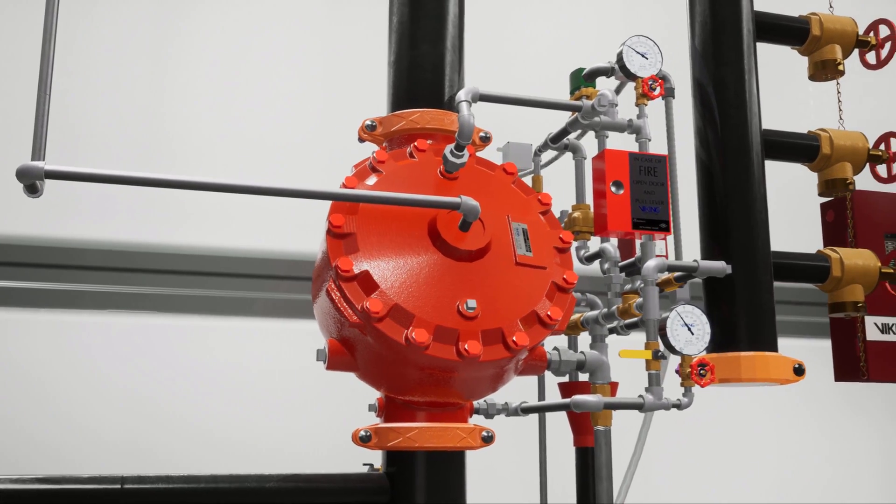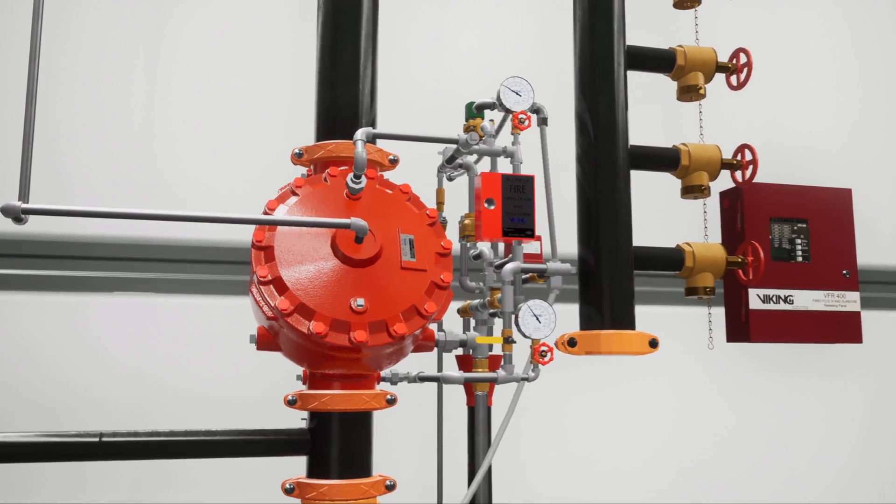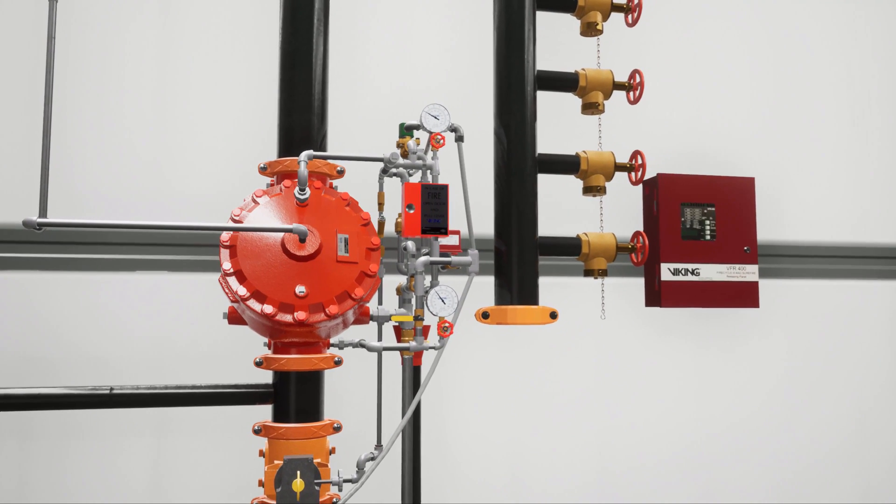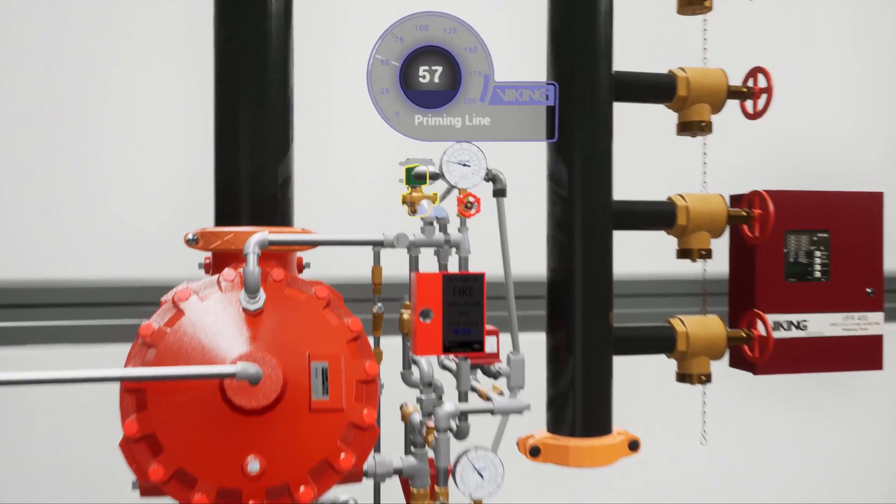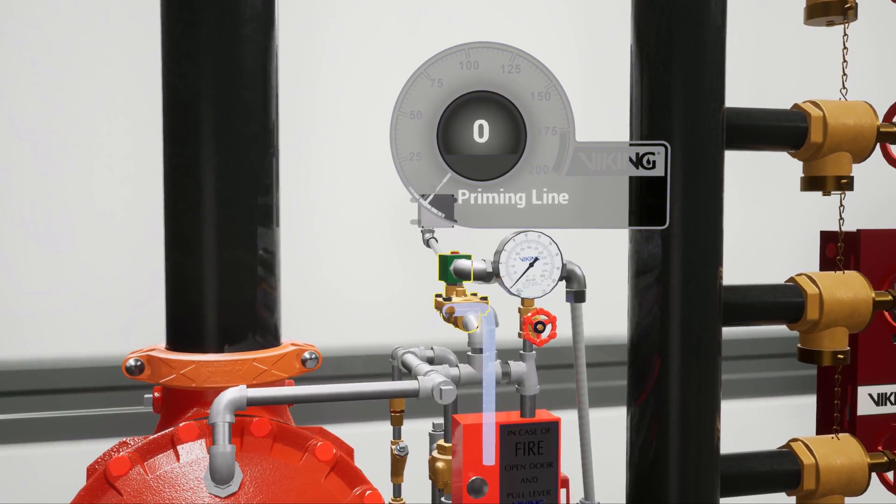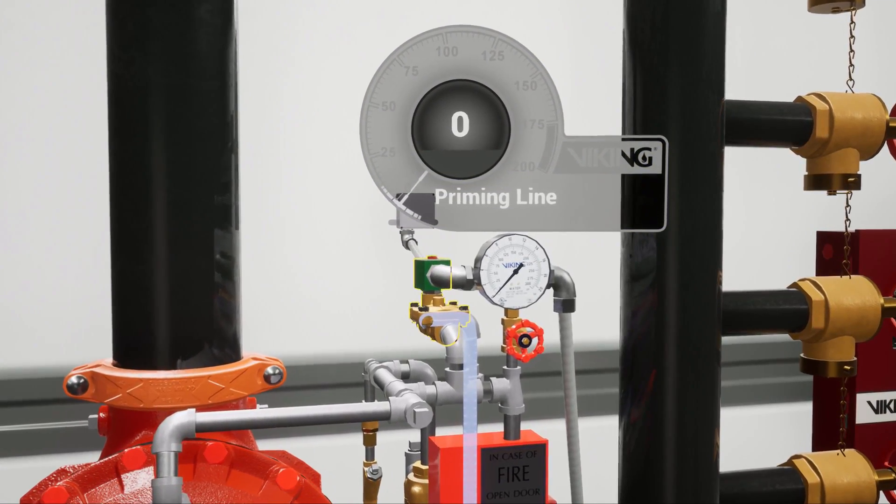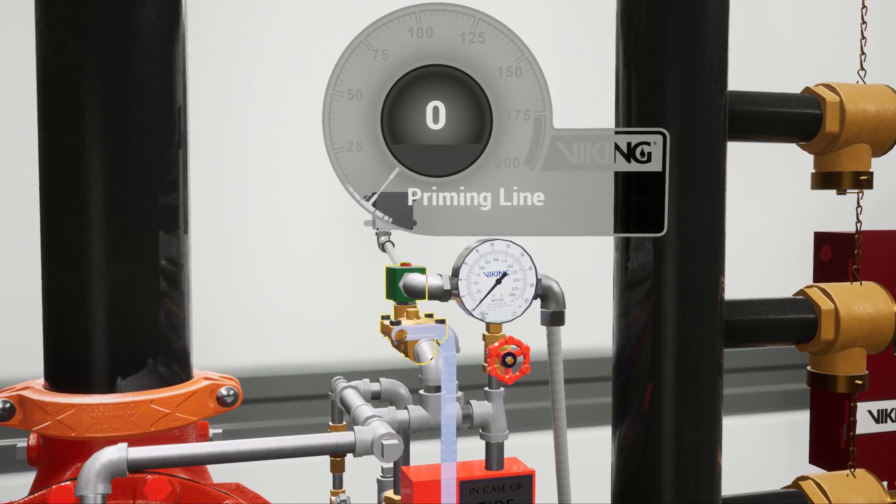In a scenario where a fire has started in the hangar and begins to grow, the electric detection device activates and sends a signal to the VFR 400 release control panel. The electric solenoid valve is powered open, releasing water pressure within the priming chambers of the deluge valve and the concentrate control valve.